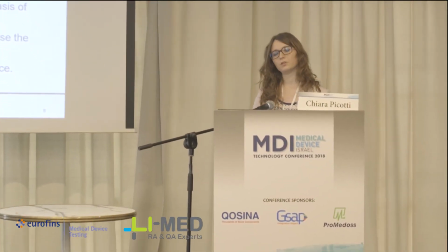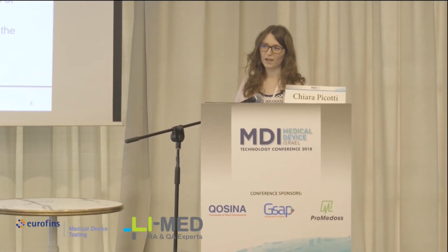And thanks to this categorization, we are able to identify the biological effects that can be considered relevant for our medical device. And for sure, considering all this information, physical and chemical information of the medical device, already existing data about toxicology, about preclinical tests, and performing the tests whose protocols are included in the ISO 10993 series standard, we can demonstrate that the device is biocompatible.